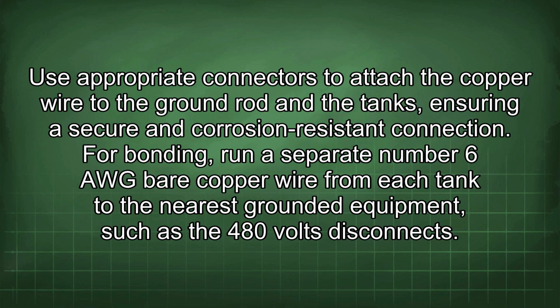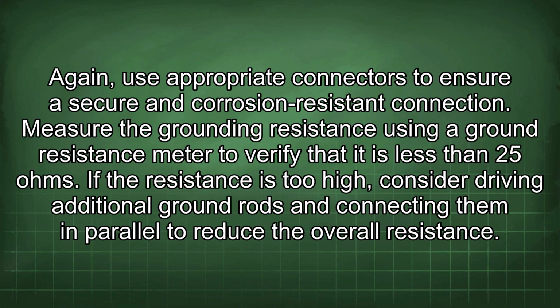Use appropriate connectors to attach the copper wire to the ground rod and the tanks, ensuring a secure and corrosion-resistant connection. For bonding, run a separate number 6 AWG bare copper wire from each tank to the nearest grounded equipment, such as the 480 volts disconnects. Again, use appropriate connectors to ensure a secure and corrosion-resistant connection. Measure the grounding resistance using a ground resistance meter to verify that it is less than 25 ohms.